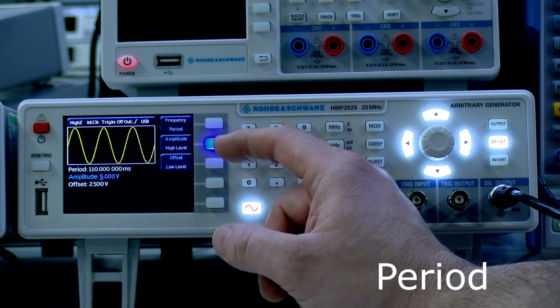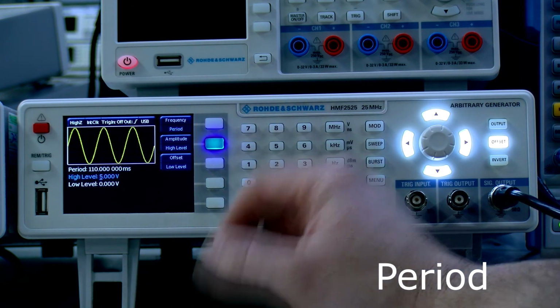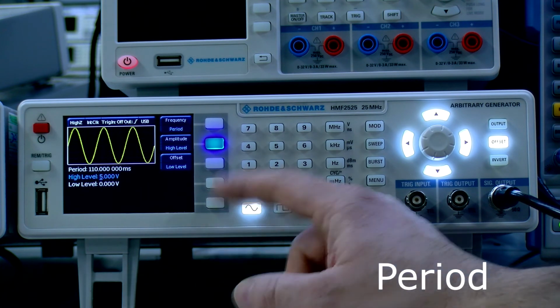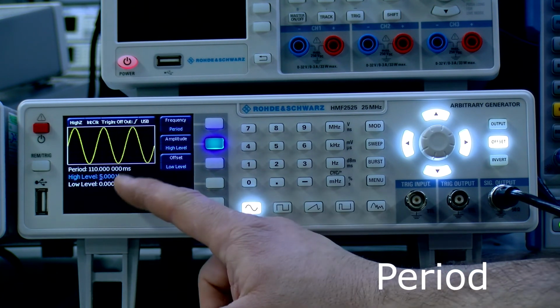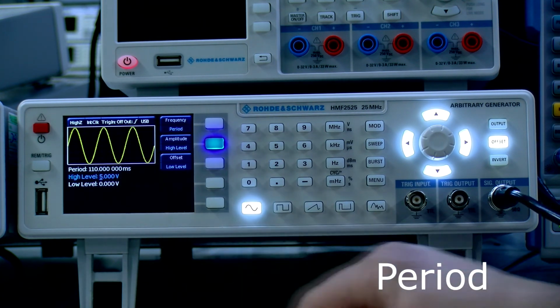And instead of doing the offset, you can choose high, low level. So again, double tap that key, high level will select, the offset will also change to low level. So you can see it's brought through our 5 and 0, which is what we had it set to.